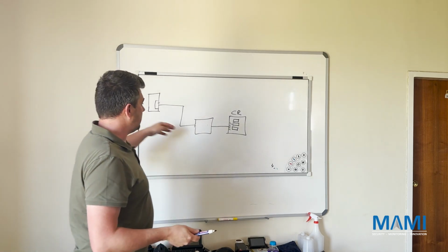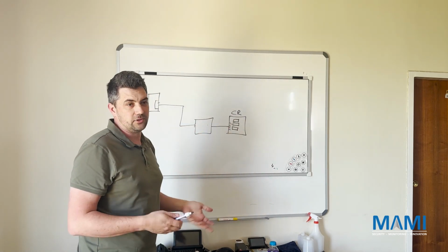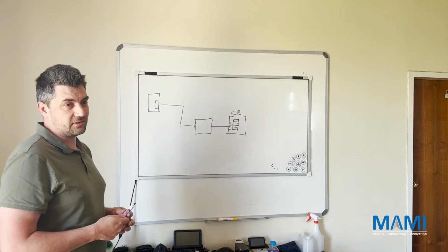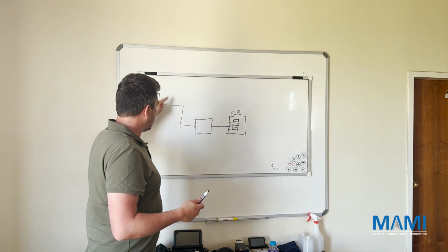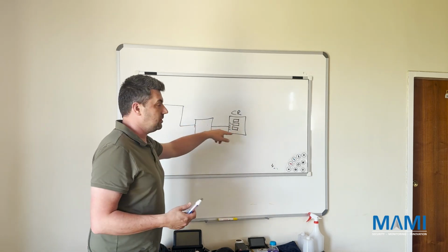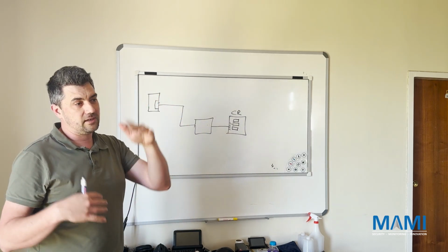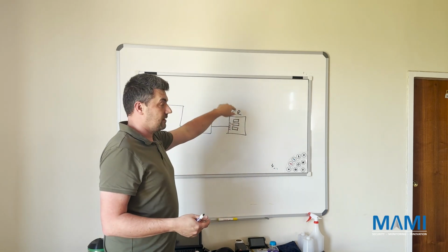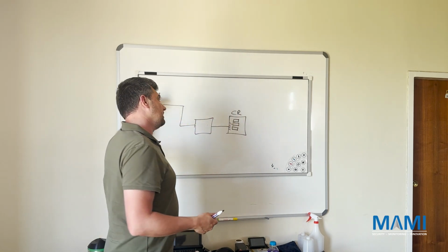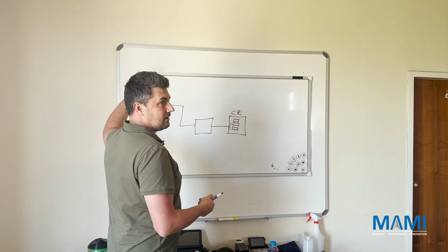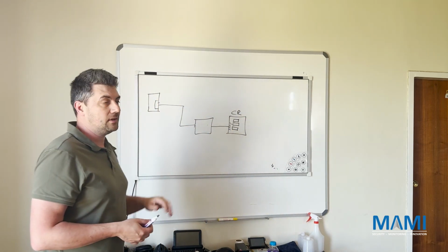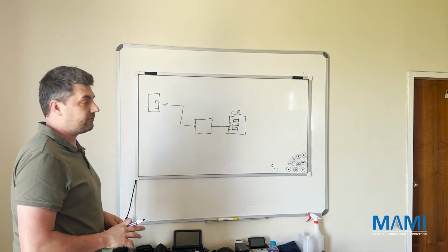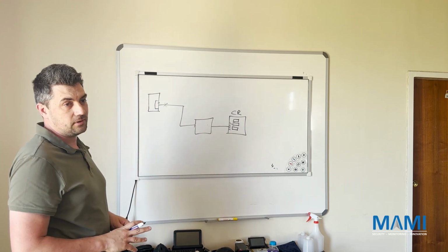So it means that you could only receive signals when that line was free, because you can't phone an engaged line. Okay, so this is old school. This is 30, 40 years ago. So it would dial, and between here and here you'd have a communication of all sorts of tones, saying acknowledge, yes, I've received the signal, this is my signal. It dialed the number. This answered, it says, send me your signal. It sent the signal, and it sends back the acknowledge to say, okay, I've received your signal, and then just terminates the phone call, and that's how the control room received the signal.